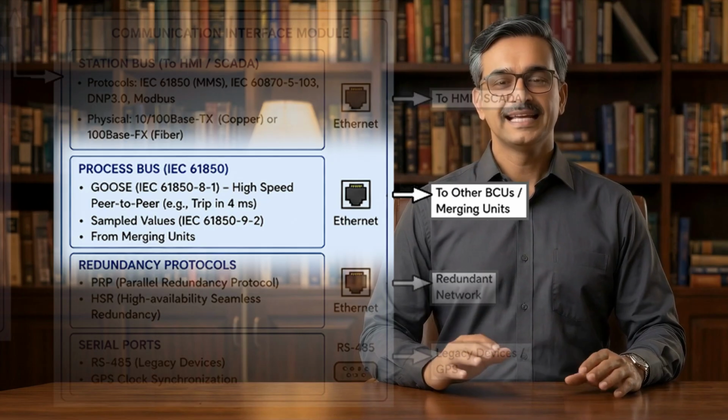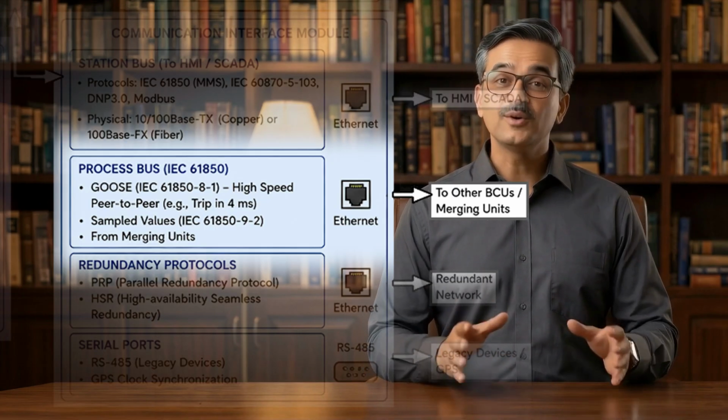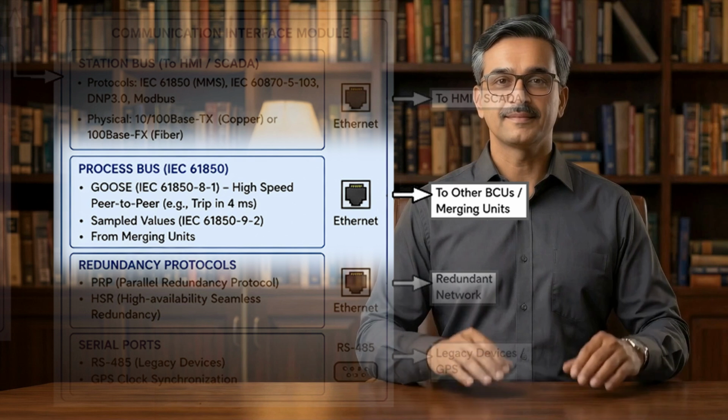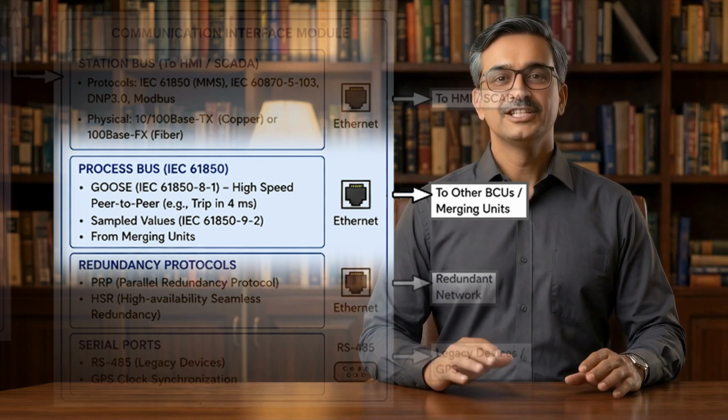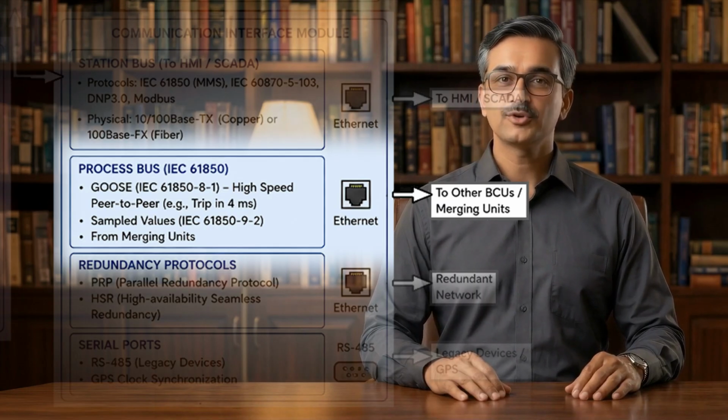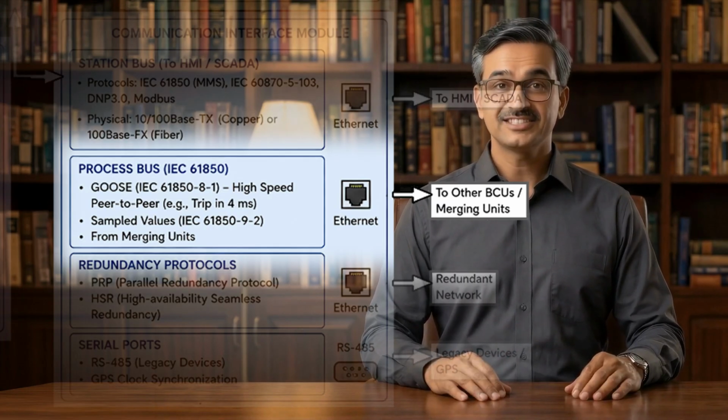It supports IEC 61850-8-1. Second, Sampled Values or SV, which receives digitized current and voltage data from merging units following IEC 61850-9-2.